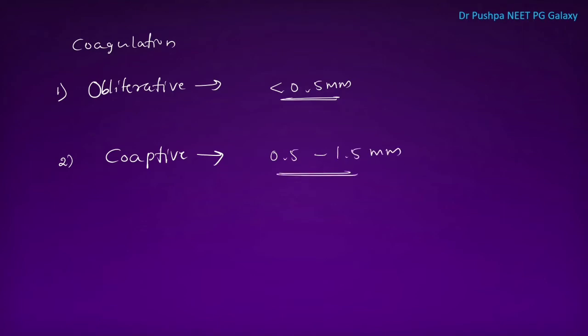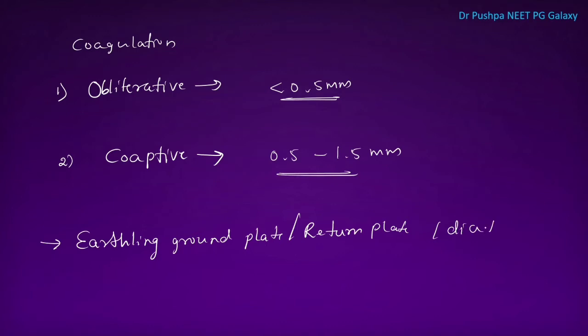In obliterative coagulation, we directly touch the bleeders with the cautery. In coaptive method, we catch the vessel with an artery forcep and apply current to the instrument. For monopolar cautery, a grounding plate — also called the return plate, diathermy plate, or diathermy pad — is required. This cautery plate should not be placed near scars or implant sites; it should be placed under a muscular, well-vascularized area like the buttocks, thigh, or back. Burn injury can develop if the plate is not properly in contact with the patient, if there are improper or broken connections, or if high voltage and high power settings are used.